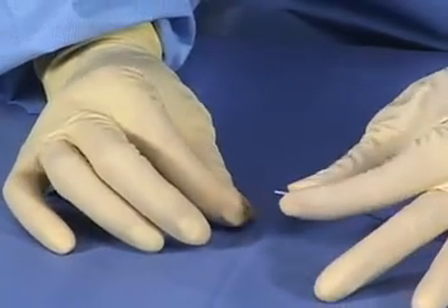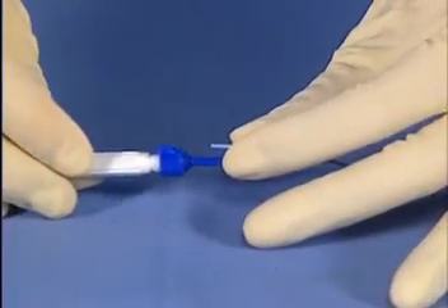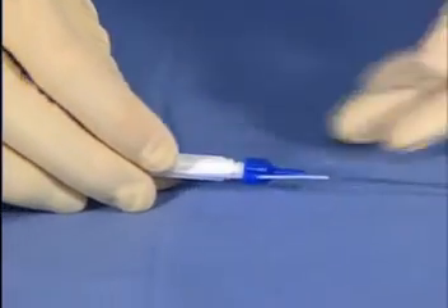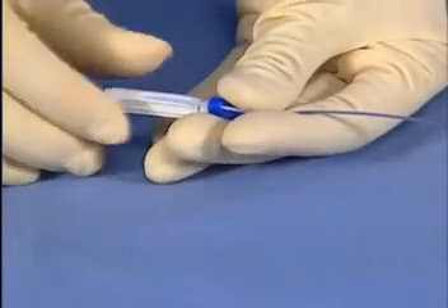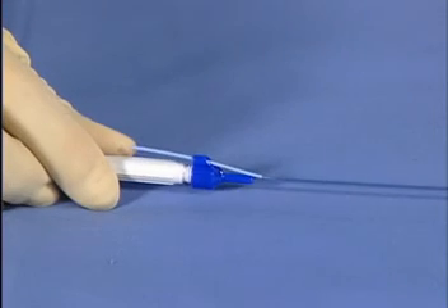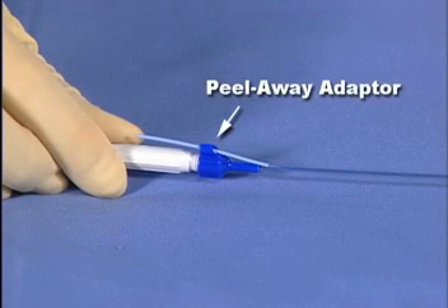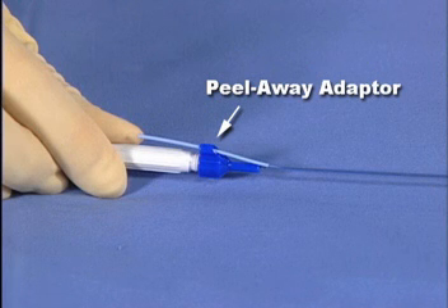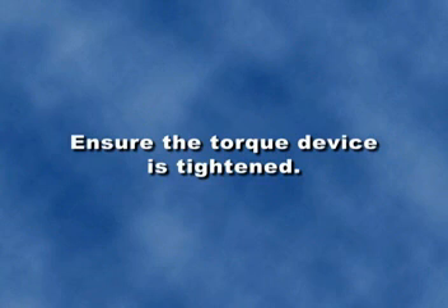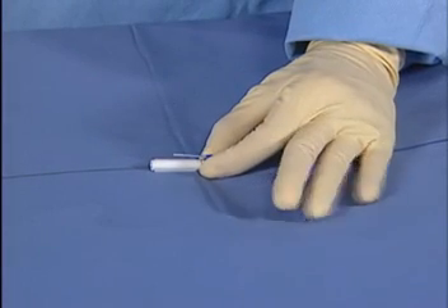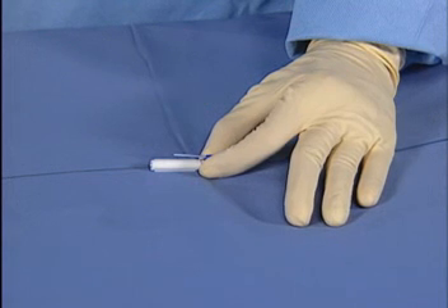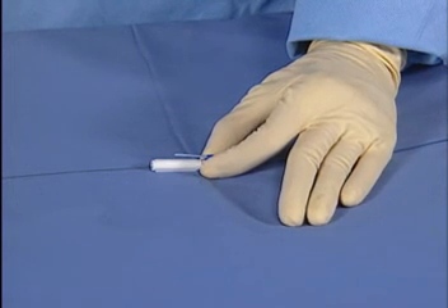Then, lift up the light blue proximal end of the delivery sheath, the portion of the sheath that has a pre-formed split in the polymer, and thread the light blue polymer into the peel-away adapter on the torque device until the tip of the collet tube is at the position where the delivery sheath splits off from the guide wire. Ensure the torque device is tightened. Remove all slack from the delivery system and stabilize the torque device with one hand.